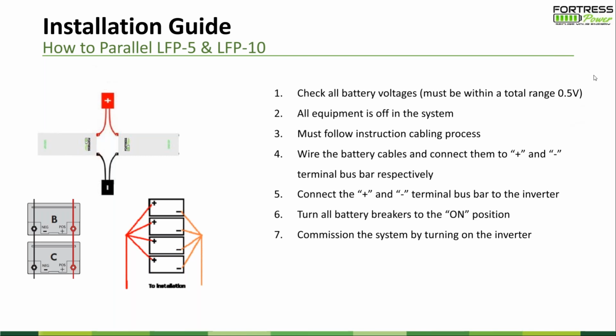As I mentioned, a couple of steps we want to follow. So make sure you check the battery voltage first. That's very important. No matter if you do this or lead acid, you always do that. And make sure all the equipment is off, nothing is on. We want to do battery wiring first. Follow the cabling processes. I mentioned the two ways we recommend. DC chain for 2 batteries only. More than 2 batteries, you go with the same length wiring system. And then do positive and negative separately, and then once you have it up, with everything going to the positive and negative bus bar, turn on all the batteries and commission your system. So the key takeaway here is check your voltage, follow the cabling processes and the instructions. Next slide, please.